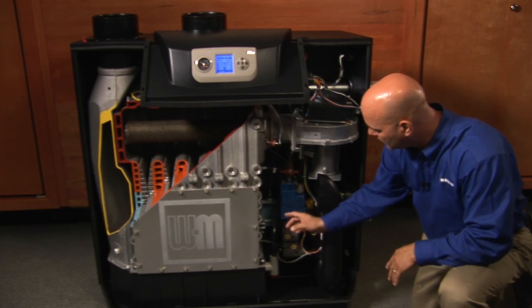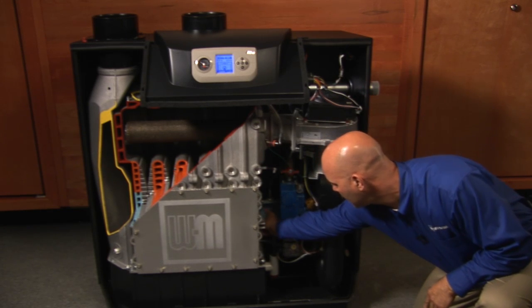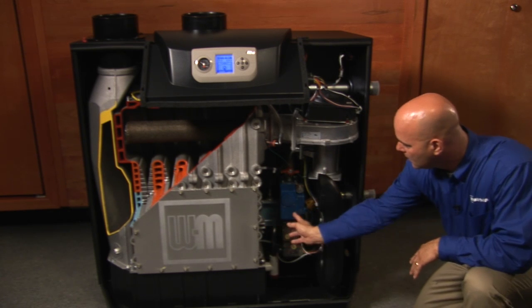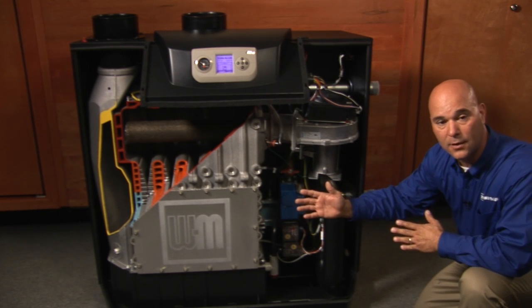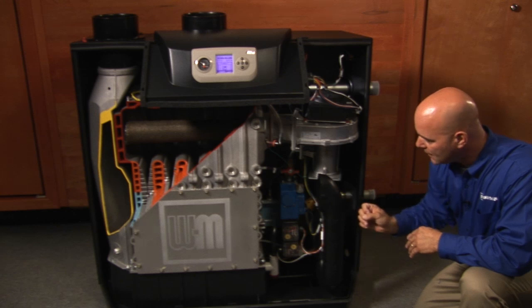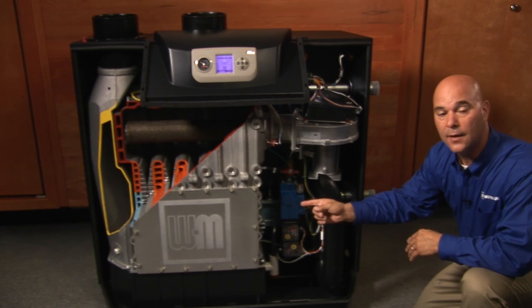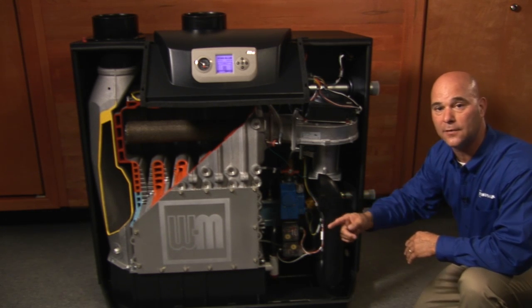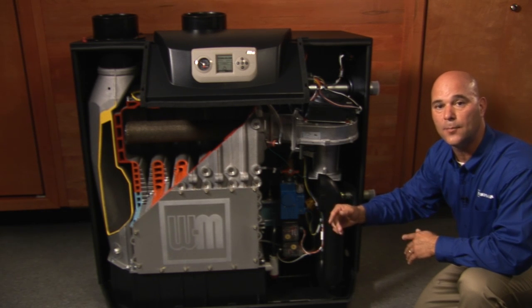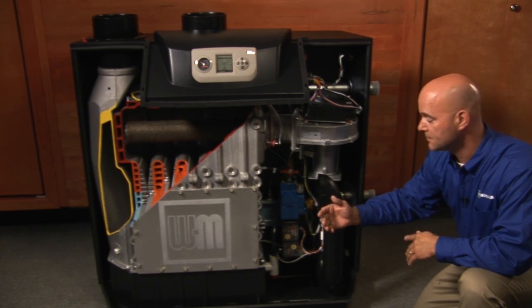And then we drop down a little bit further, and we have a cutaway of the return tapping. There are diverter tubes that go in the return port. They go down along the whole length of the boiler, and they make sure we have the correct amount of flow to each section so we can keep all of our sections at the same temperature.